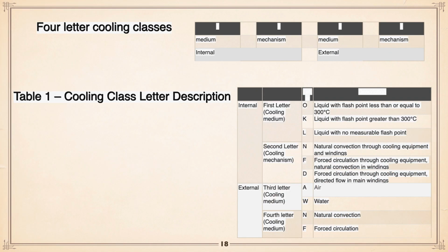What they mean is, to begin with, by the way, you're dealing with internal medium and mechanism, external medium and mechanism. That's the 1, 2, 3, 4. So the first, internal. First letter is cooling. Liquid with a flash point less than or equal to 300 C, basically transformer oil. So that's the O. There are options you can work your way up on, but O will be the most common. N, how are you cooling it?